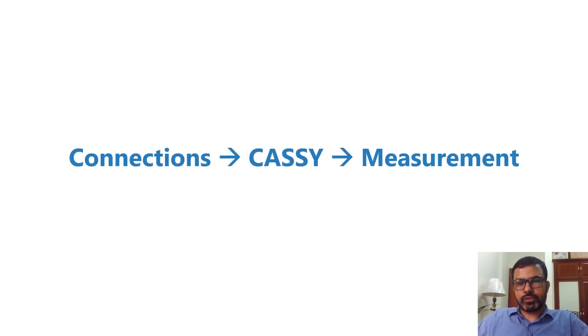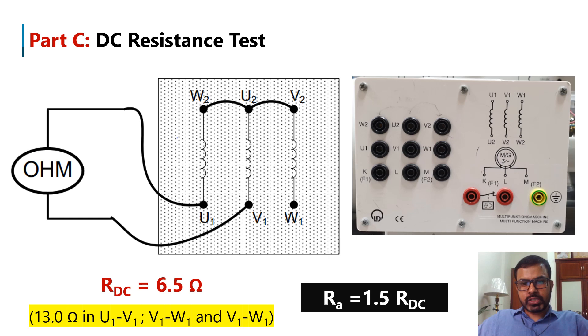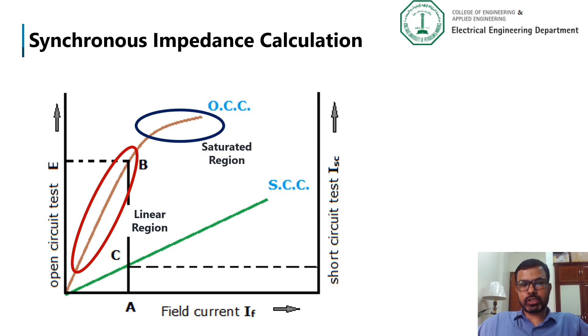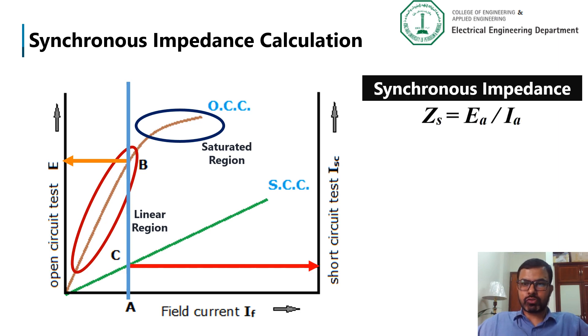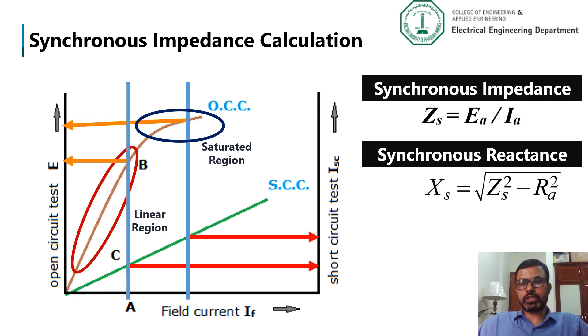After making the circuit connections, we will record the required measurements in the CASSY software. Part C of this experiment is the DC resistance test, from which we calculate the armature resistance of the synchronous generator. From the recorded measurements, you will obtain a graph with a linear region and a saturated region. Drawing a straight line through the linear region and plugging the corresponding voltage and current values into the equation gives the synchronous impedance. From the synchronous impedance and armature resistance, you can obtain the synchronous reactance. These parameters can similarly be determined in the saturated region.